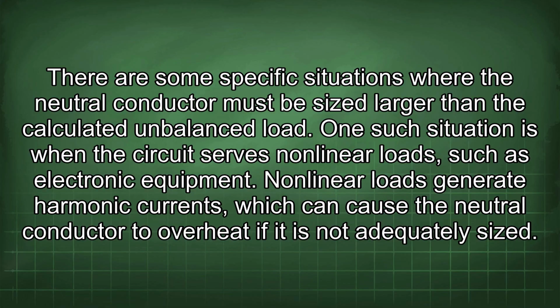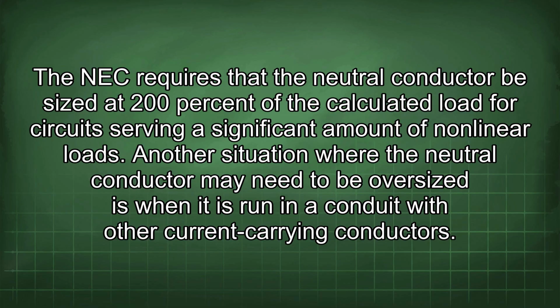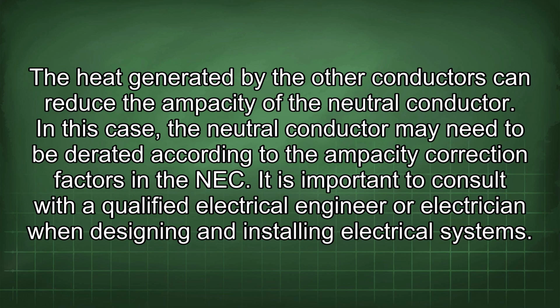Nonlinear loads generate harmonic currents, which can cause the neutral conductor to overheat if it is not adequately sized. The NEC requires that the neutral conductor be sized at 200% of the calculated load for circuits serving a significant amount of nonlinear loads. Another situation where the neutral conductor may need to be oversized is when it is run in a conduit with other current-carrying conductors. The heat generated by the other conductors can reduce the ampacity of the neutral conductor. In this case, the neutral conductor may need to be derated according to the ampacity correction factors in the NEC.